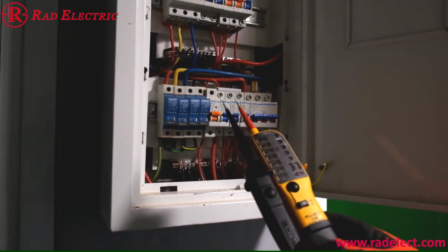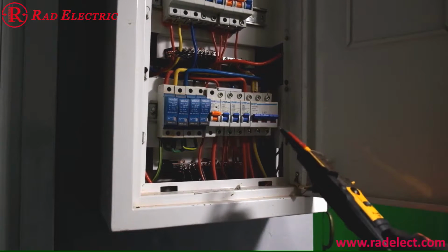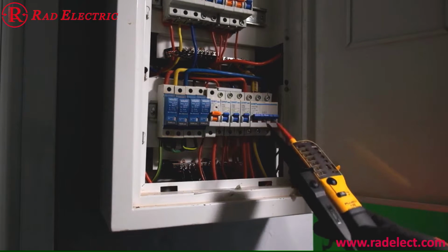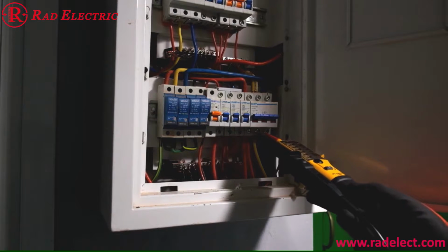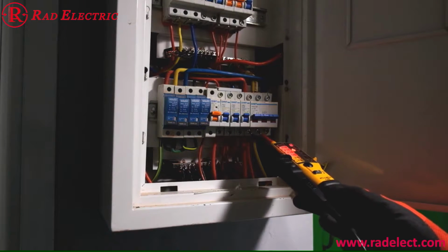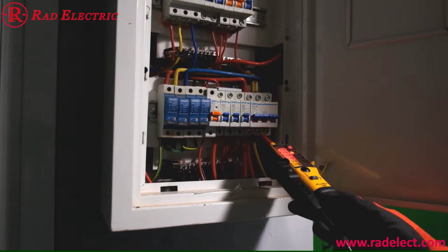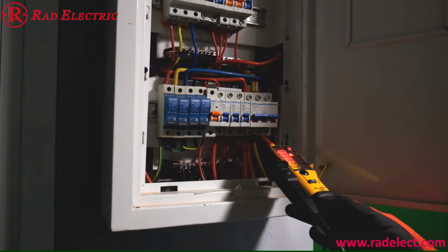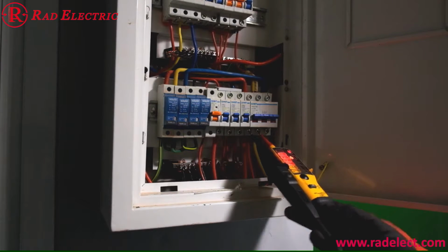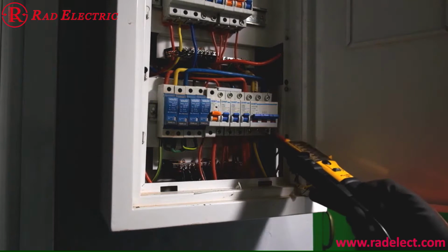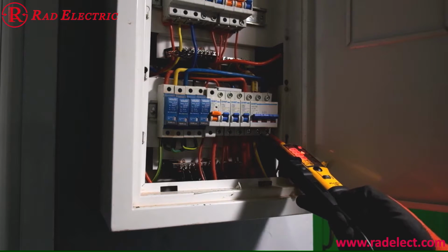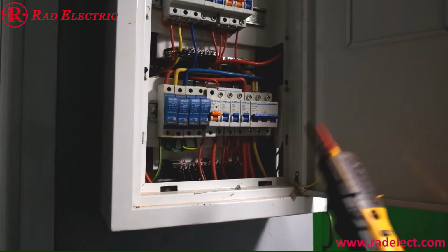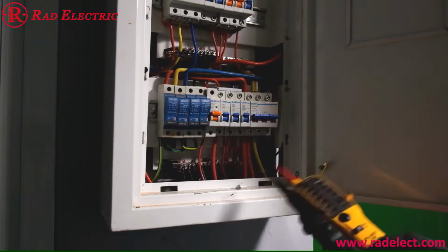Personally I believe in not having more than one point in the air, but if you wanted to test phase to phase, for example, we could go like that and it will show us we have 400 volts AC showing up on the tester, and against the other phase we should have the same thing. There we go, 400 volts AC. So we know this is our 3 phases over here.